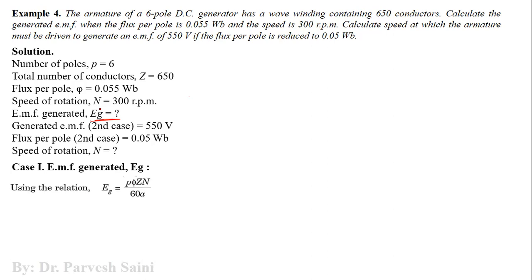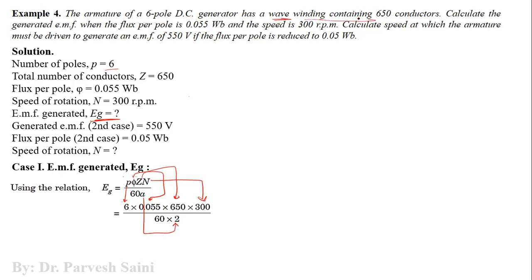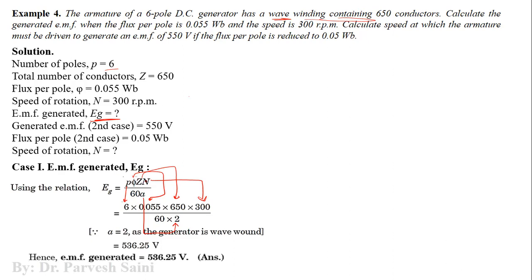For case one, using Eg = (P × phi × Z × N) / (60 × A): P = 6, phi = 0.055 weber, Z = 650, N = 300 rpm, A = 2. Solving this equation gives the generated EMF as 536.25 volts.